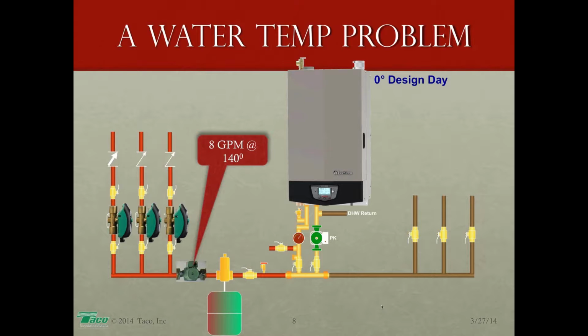If I apply my universal hydronics formula, I find that my gallons per minute will be equal to 80,000 BTUs divided by my designed-for delta T of 20 degrees, 20 times 500, or 10,000. 80,000 divided by 10,000, that is a header load of 8 gallons per minute. So my header down here has to be sized to deliver 8 gallons per minute. In a normal world, that would be 1-inch pipe. In the world of ModCons, it might behoove us to go up to 1.25 inches, even 1.5 inches.